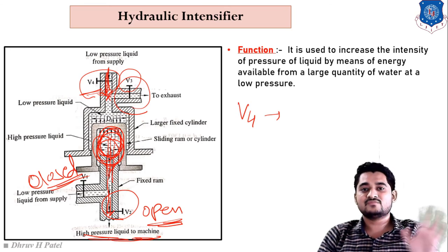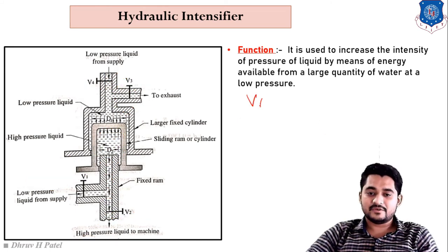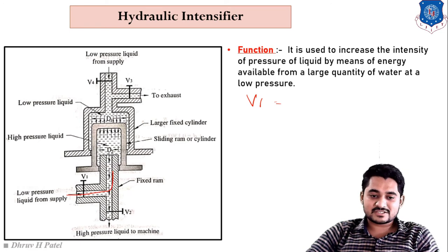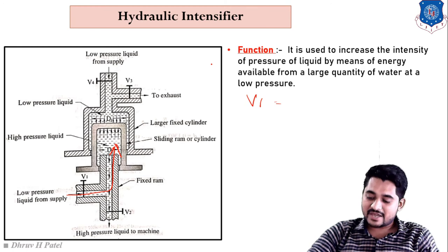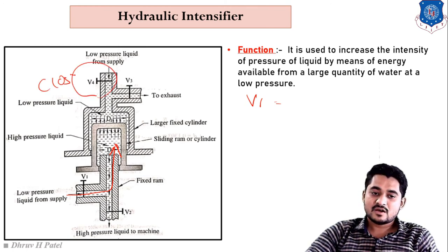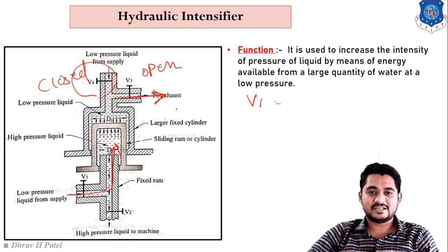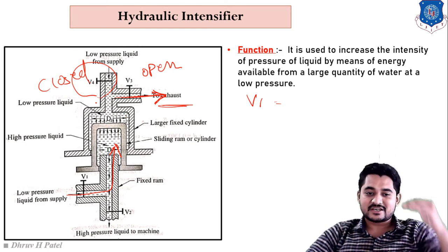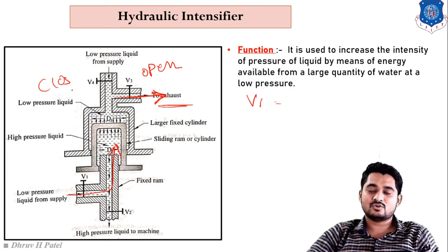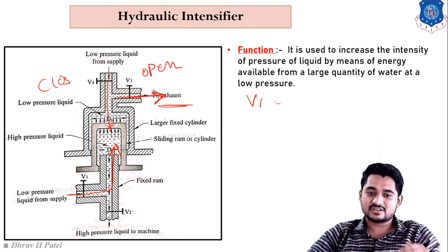The procedure is then repeated. V1 valve is opened again so low-pressure liquid flows in and is stored in the sliding ram section, moving the sliding ram upward. V4 is closed, but V3 (exhaust valve) is opened so exhaust fluid exits. Once the sliding ram reaches its upper position, V4 is opened again.